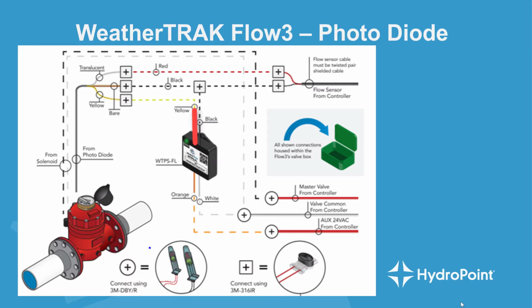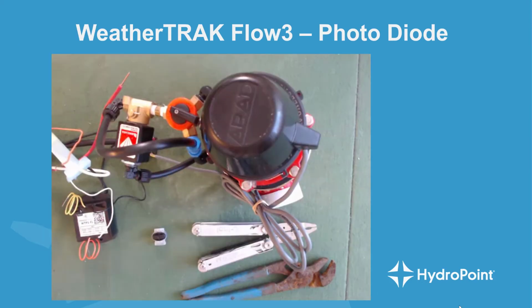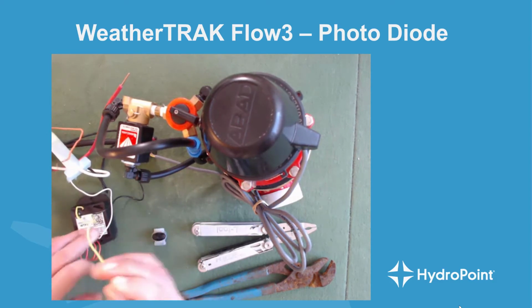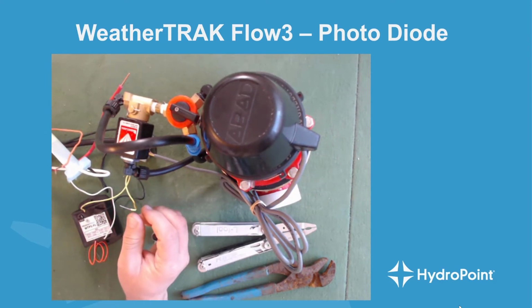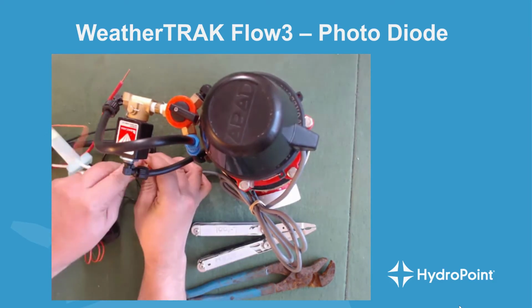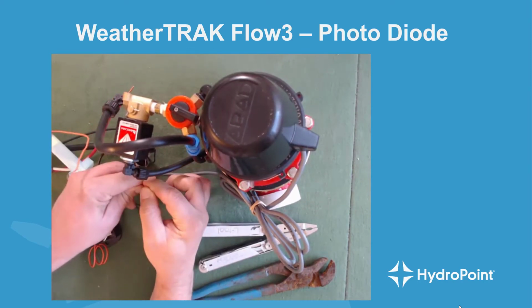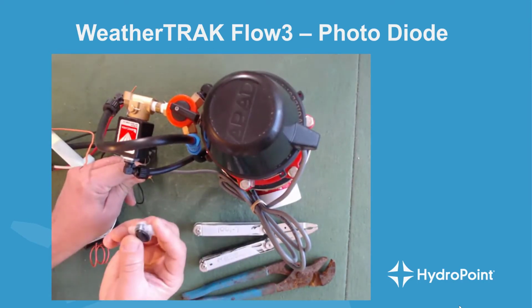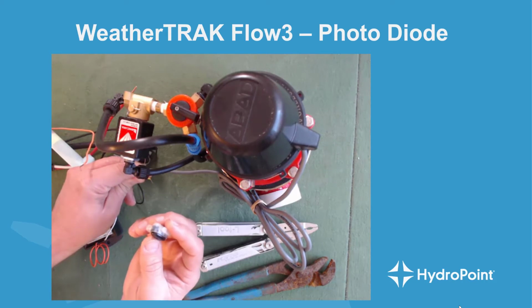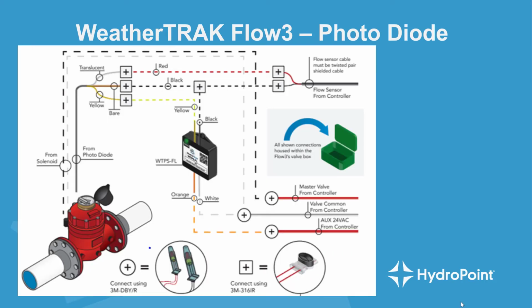Specifically, we'll take this yellow wire from the power supply and connect it to the yellow wire from the flow sensor. In the valve box, it looks like this. We go to our power supply, grab the yellow wire, and connect it right up to the yellow wire on the flow sensor using the 316 IR wire connector. Next, we'll finish off our flow sensor wire by finding the translucent wire and connecting it to the red wire, or the FL positive, in our shielded flow sensor wire coming from the controller.